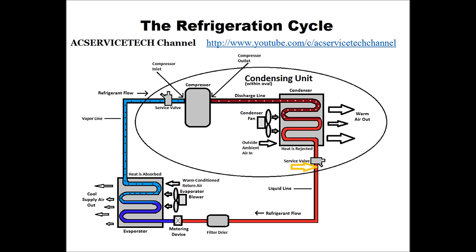That is called subcooling — the temperature decrease in liquid form. It continues to go through the refrigerant line until it goes through the filter dryer, which absorbs any moisture in the refrigeration system, and then it hits the metering device where there's a pressure drop. It drops from high pressure, high temperature liquid refrigerant to a low pressure, low temperature 80% liquid, 20% flash gas, but mainly liquid.